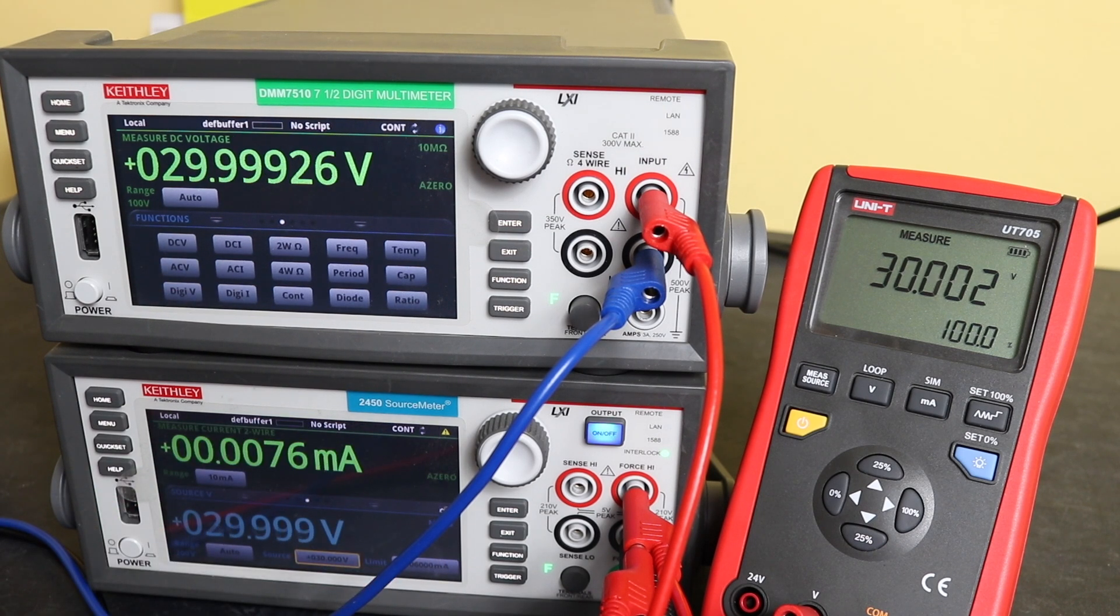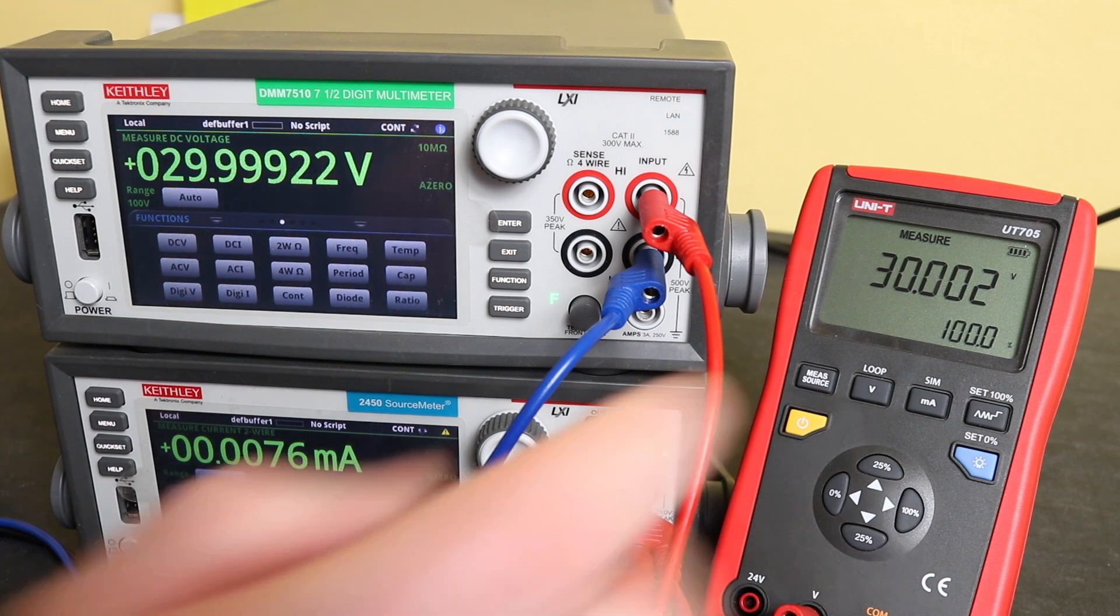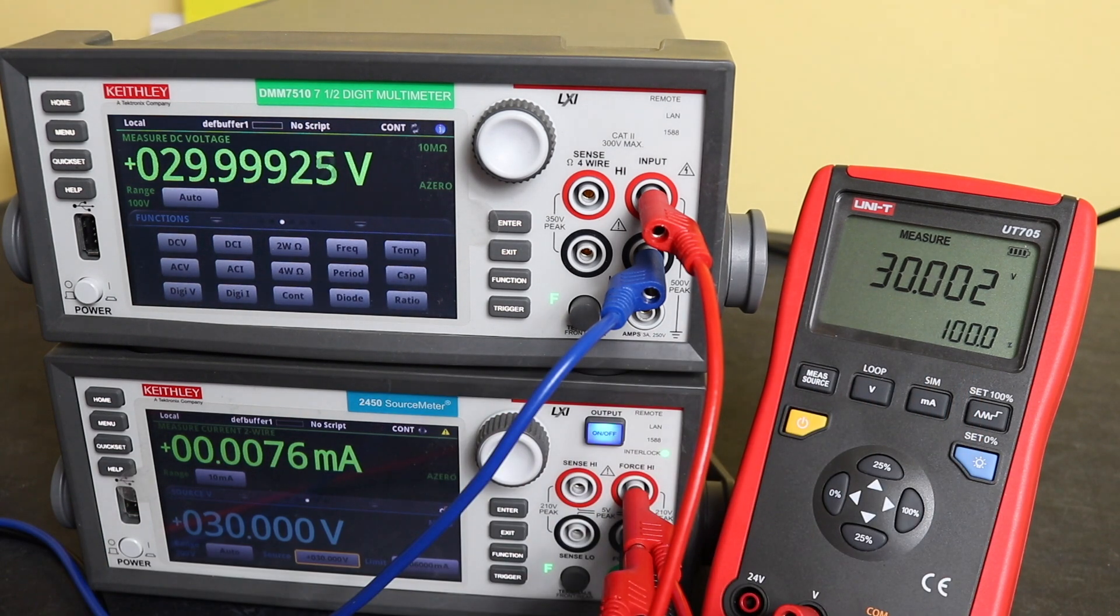And our final one is 30 volts. So there's our final measurement there. 30 volts, we are reading 30.002. Correlates pretty well, 29.99926 on the 7510 there. Tolerance-wise we should be between 29.992 and 30.008 on the unit, so well within specification and our scaling there is 100 percent. Excellent. So we'll have a quick shuffle around again and we will do some milliamp source checks.